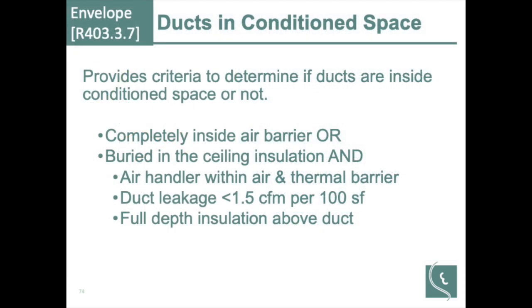As far as ducts in the conditioned space, how do we determine if a duct is in the conditioned space, particularly if you're doing some energy modeling? It calls out 3 criteria. Obviously, if it's totally inside the air barrier, it's totally in the conditioned space. Or if it's buried in the insulation and it has these criteria: normal duct leakage, you're allowed 3 CFM per 100 square feet. So these have to be half the air leakage rate or less than a typical duct, and then obviously your insulation.